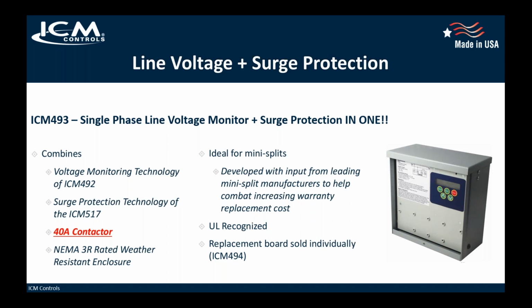Now, granted, in the mini split market, voltage problems are the worst. So minimum security would be just a voltage monitor. The big problem with the mini split market is that a lot of mini splits are rated for 208/230, and we have 240 in the U.S. In our 240, we'll usually have like a 10% tolerance, so you might be starting out at 247, 248, but the mini splits are rated for 208/230, which leaves you with 253 as the maximum that they want to see. If you even go a few volts above this 253, it will damage the circuit board, and they're non-repairable. A lot of times you have to replace the circuit boards.